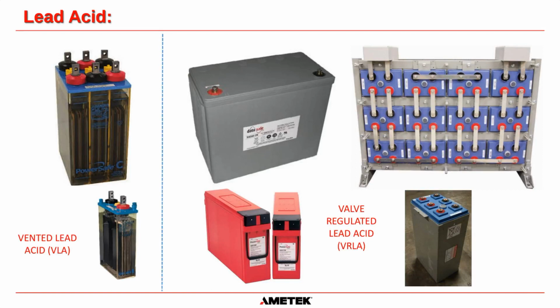Okay, we have a positive lead plate and we have a negative lead plate, and there is a sulfuric acid electrolyte inside them. They are identical in their chemical makeup. It's just how the electrolyte is contained in these valve regulated cells that is different. So in the wet cells or the vented lead acid cells, it is a solution that is very similar to water. In a valve regulated lead acid cell, it's usually either in an absorbed glass mat, in other words, like a fiberglass type mat between the plates that absorbs the electrolyte, or it's in a gel solution. So in both circumstances, if you cut open one of those batteries, in theory, no electrolyte is supposed to leak out.